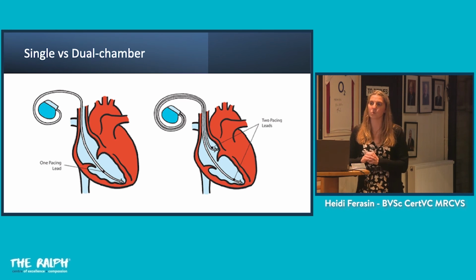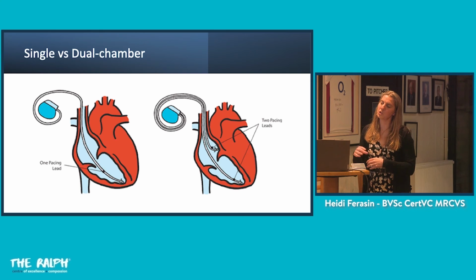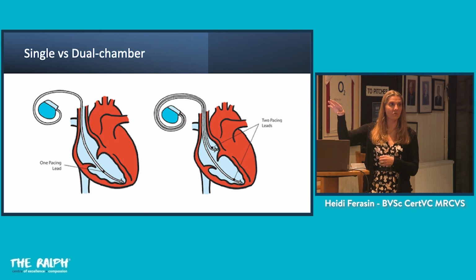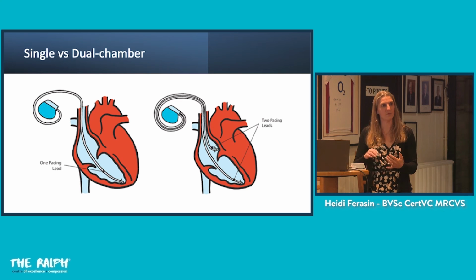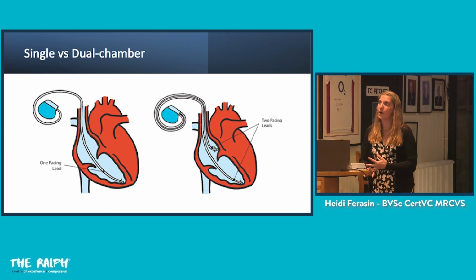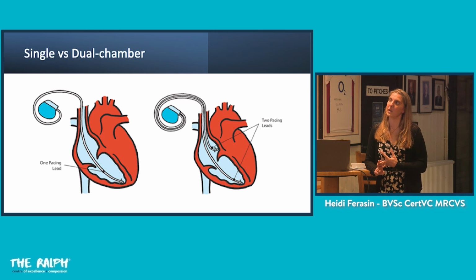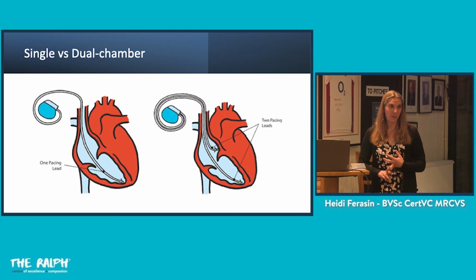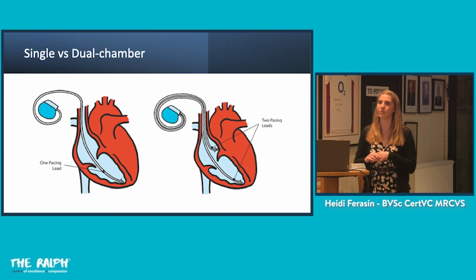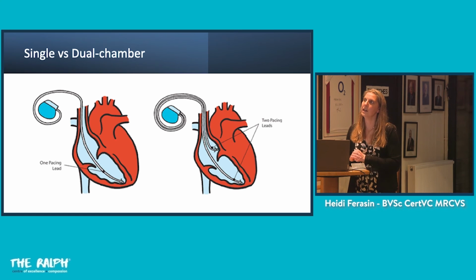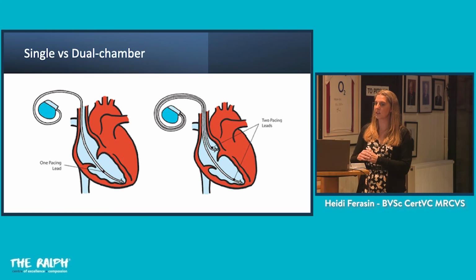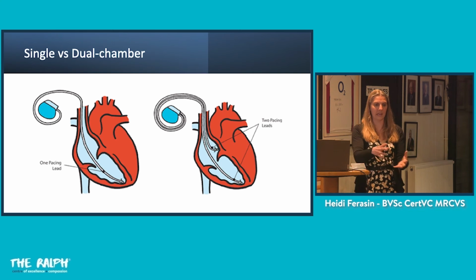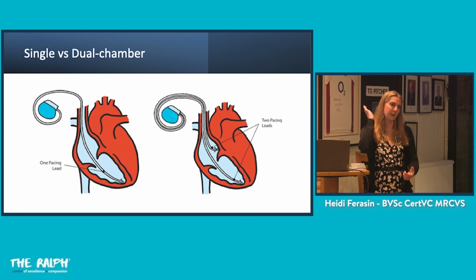The pacemaker programmer works with radio signal to allow us to program the information that we want into the pacemaker device: tell it how fast to beat, what the minimum rate we want it to beat at is, what the maximum rate is, and when we want it to kick in. We can also draw information from the pacemaker, telling us how much battery is left, how much the patient's been relying on the pacemaker, what the activity has been, and therefore what the impedance and the resistance through the lead is, etc. So it's a really key piece of kit. It's like a computer, and it has a cable, and on the end of the cable it looks like a computer mouse, and you literally place that over the skin of the patient, overlying where the pacemaker is, and it reads all that information and programs the device accordingly.